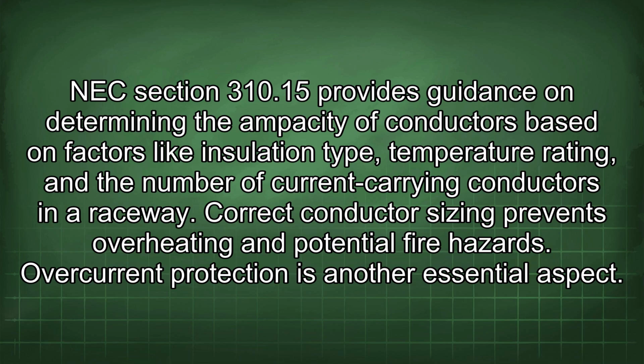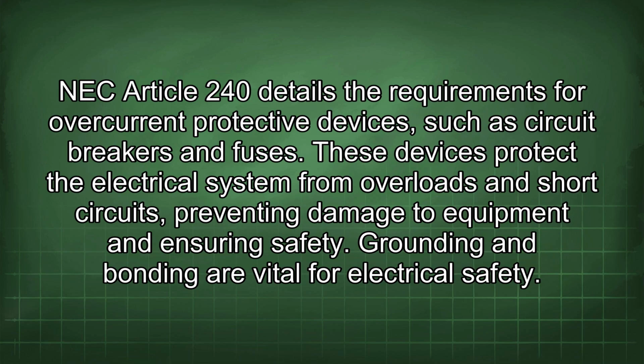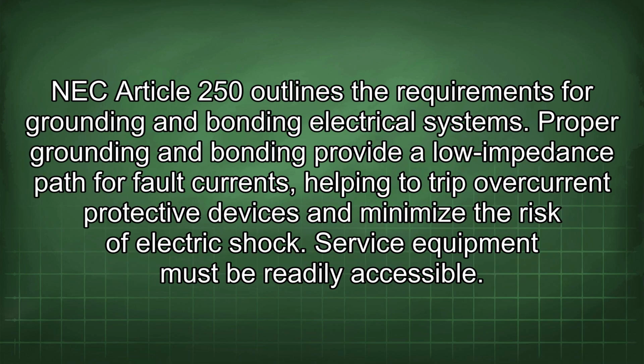Overcurrent protection is another essential aspect. NEC Article 240 details the requirements for overcurrent protective devices such as circuit breakers and fuses. These devices protect the electrical system from overloads and short circuits, preventing damage to equipment and ensuring safety. Grounding and bonding are vital for electrical safety. NEC Article 250 outlines the requirements for grounding and bonding electrical systems. Proper grounding and bonding provide a low impedance path for fault currents, helping to trip overcurrent protective devices and minimize the risk of electric shock.